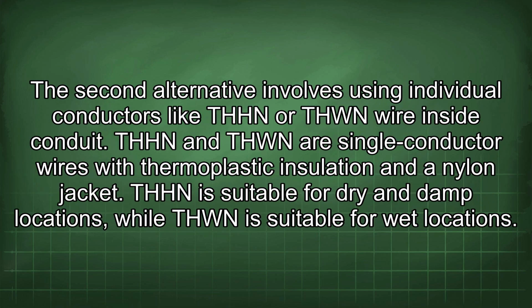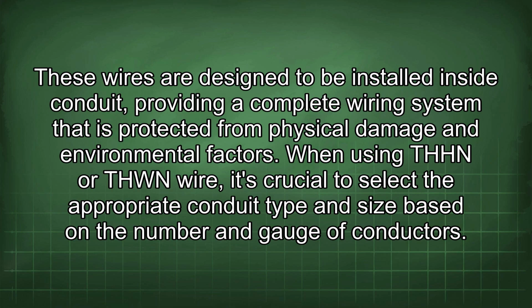The second alternative involves using individual conductors like THHN or THWN wire inside conduit. THHN and THWN are single conductor wires with thermoplastic insulation and a nylon jacket. THHN is suitable for dry and damp locations, while THWN is suitable for wet locations. These wires are designed to be installed inside conduit, providing a complete wiring system that is protected from physical damage and environmental factors. When using THHN or THWN wire, it's crucial to select the appropriate conduit type and size based on the number and gauge of conductors.